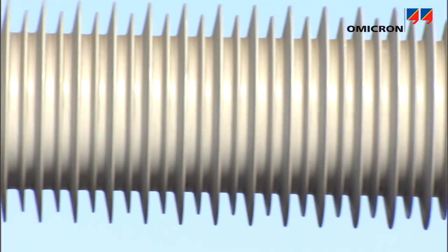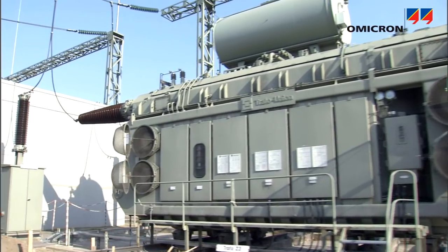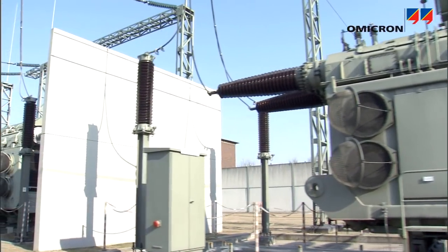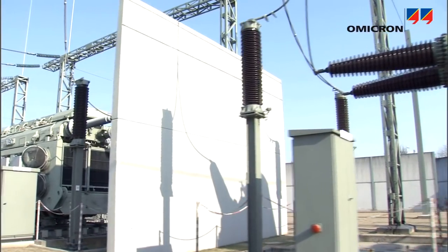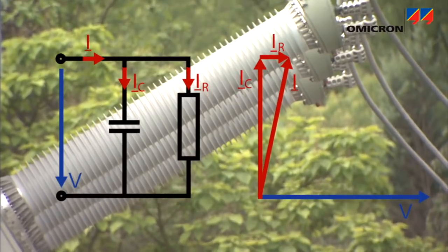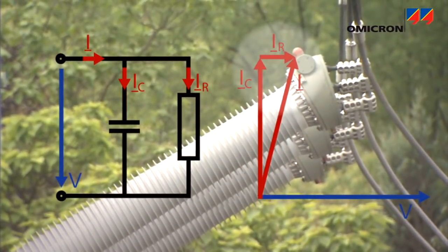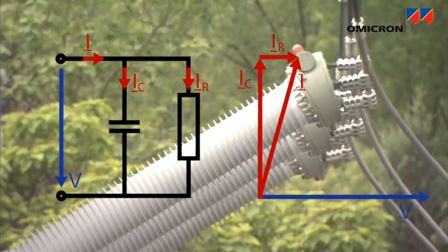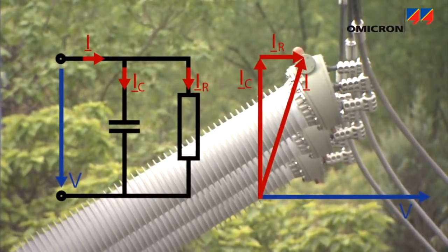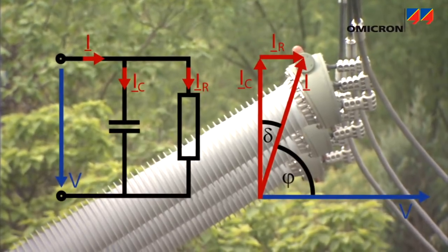The condition of the bushings and the overall insulation of power transformers can be investigated by measuring the capacitance and dissipation factor, also known as the tangent delta or power factor. Aging and decomposition of the insulation, or the ingress of water, increases the losses and thus more energy is turned into heat in the insulation. The level of this dissipation is expressed by the dissipation factor or power factor.